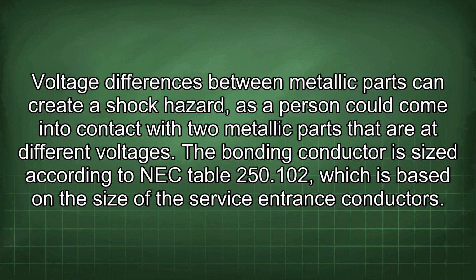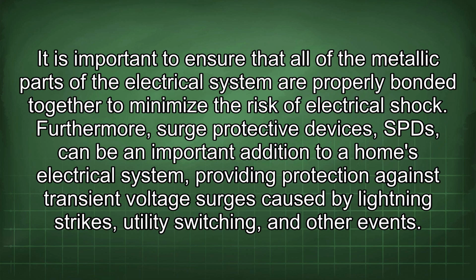The bonding conductor is sized according to NEC Table 250.102, which is based on the size of the service entrance conductors. It is important to ensure that all of the metallic parts of the electrical system are properly bonded together to minimize the risk of electrical shock.